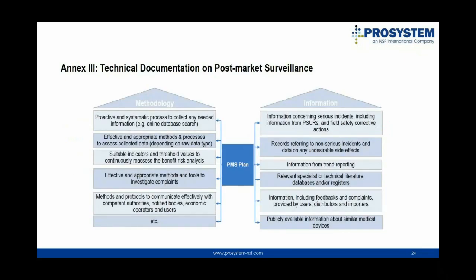The PMS plan needs to specify active and systematic procedures to gather various information, such as information concerning serious incidents, including information from other PSURs and field safety corrective actions. Ideally, you would reference your existing vigilance procedures, which should be streamlined with the MDR vigilance requirements in Articles 87 to 92. Furthermore, Annex 3 provides detailed requirements regarding the specification of data gathering, as well as analysis and evaluation methods, such as suitable indicators and threshold values.